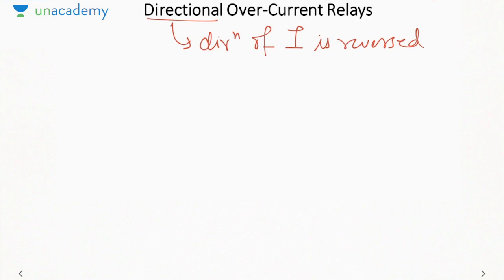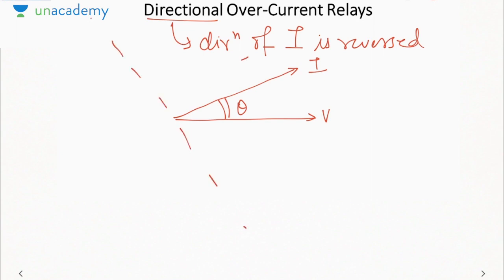So how does a directional overcurrent relay operate? A directional overcurrent relay operates when the torque is produced by interaction of the magnetic fields produced by the current and the voltage sources. Suppose this is my voltage phasor. Then your current is, let us say, leading. This is my current, leading by an angle theta. Because, as I told you, the relay will operate between the 0 and the maximum torque line. So there is my current line at an angle theta. This was the maximum torque line, and this was the 0 torque line. Since it is lying within this region, the relay must operate.